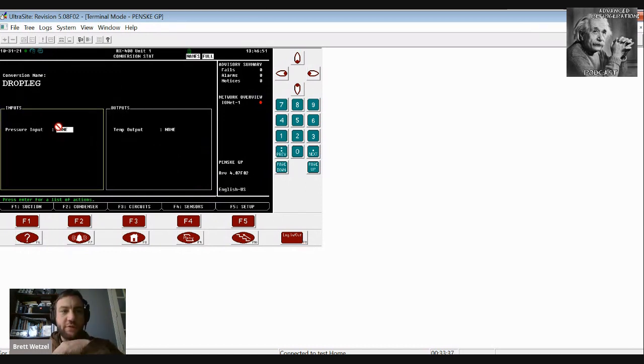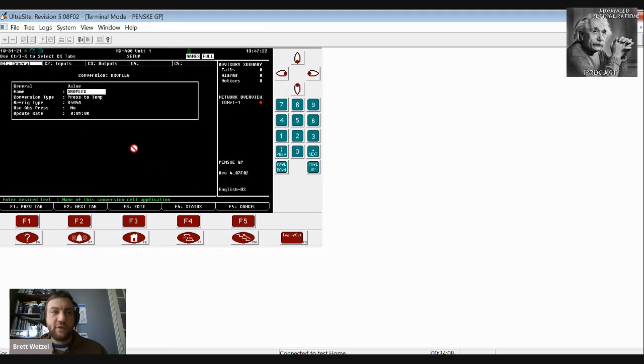See if I can override a value here. Yes. 250 pounds. So this is basically taking a refrigerant pressure and converting it to a saturated condensing temperature on this one. If we actually go to setup on this, you can see pressure to temperature, it's 404.